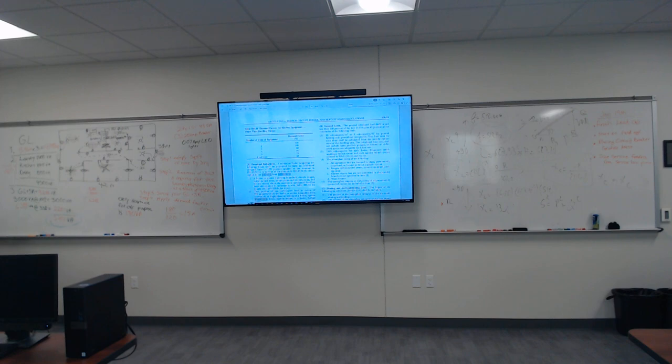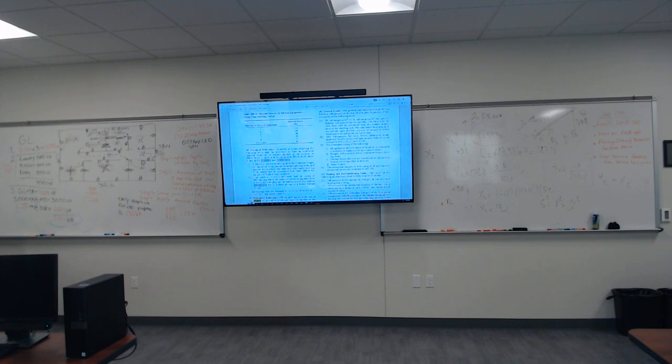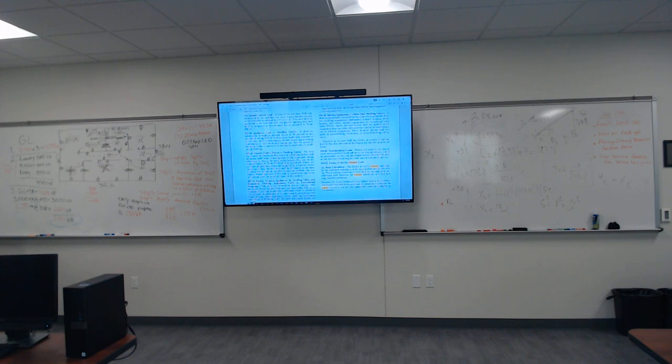It says 70% of the neutral. But let's see what the NEC says about the neutral. Y'all see this right here on the TV screen? It says permitted reduction. And let me find out what it actually says. Okay, here we go. Article 220.61, feeder or service neutral load. The feeder or service neutral load shall be the maximum unbalance of the load determined by the article.